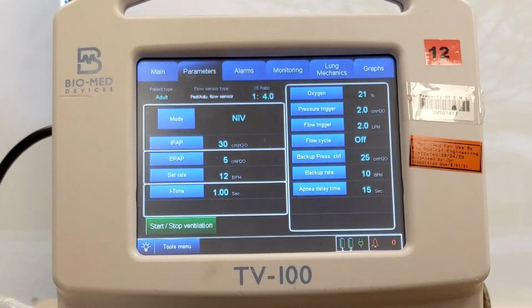NIV stands for non-invasive ventilation. In NIV mode, the TV-100 allows the clinician to set the IPAP/EPAP levels to be applied to spontaneous breaths. IPAP and EPAP stand for inspiratory positive airway pressure and expiratory positive airway pressure, respectively. IPAP is referenced to 0 and not to EPAP/PEEP, like with the Newport HT70. The clinician can provide CPAP in non-invasive modes by setting the IPAP and EPAP values to the same level.